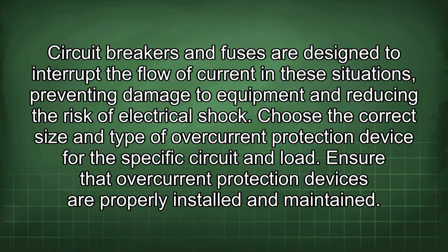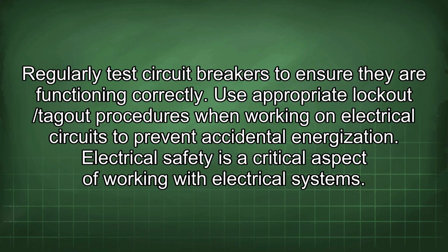Circuit breakers and fuses are designed to interrupt the flow of current in these situations, preventing damage to equipment and reducing the risk of electrical shock. Choose the correct size and type of overcurrent protection device for the specific circuit and load. Ensure that overcurrent protection devices are properly installed and maintained. Regularly test circuit breakers to ensure they are functioning correctly. Use appropriate lockout/tagout procedures when working on electrical circuits to prevent accidental energization.